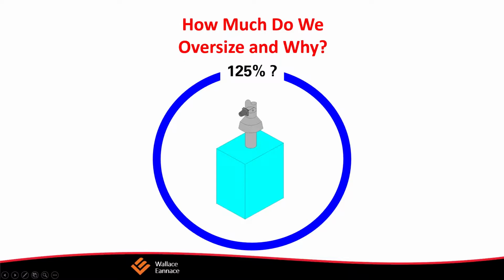And the question we may ask is, even with doing that, in the case of a simple 100,000 BTU load, you're going to have one unit. But if you have a large load in a building, how many boilers do we fit in a room? And how do we make this selection? So the first thing we have to do is look at the boiler turn down ratio. The boiler turn down is the ratio between the boiler's maximum output and minimum output. Depending upon the burner's design, it may have a turn down ratio between 5:1 and 10:1 or even higher.